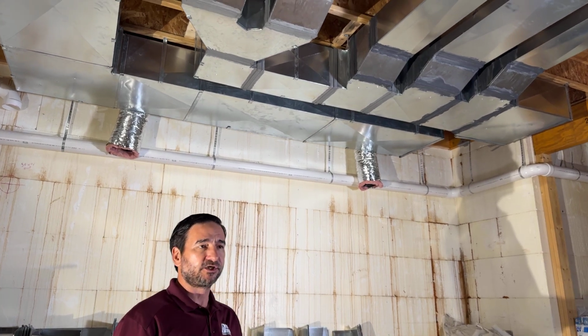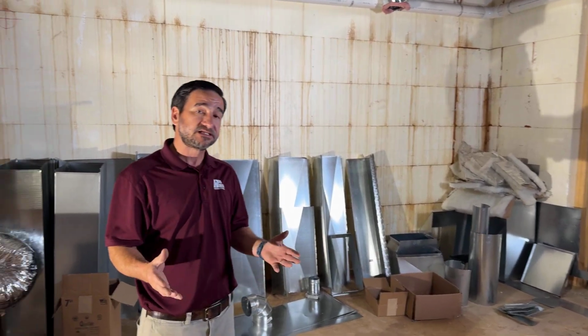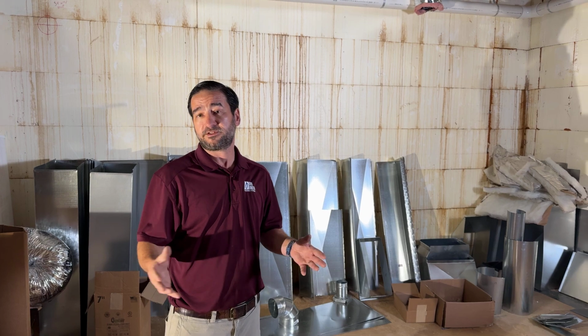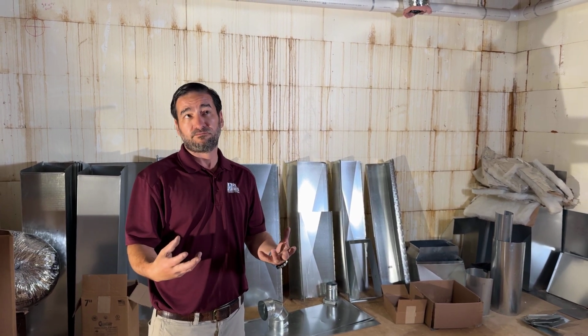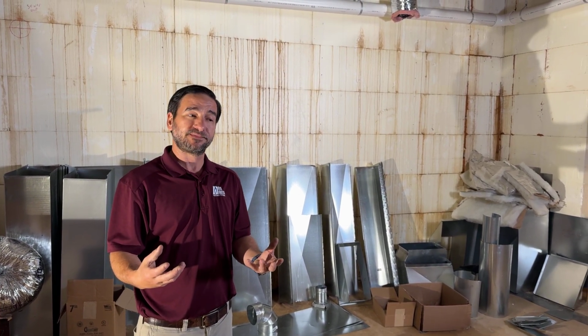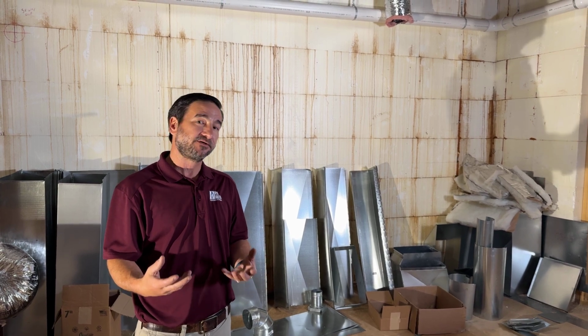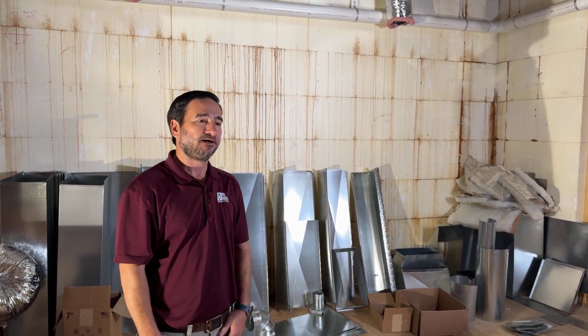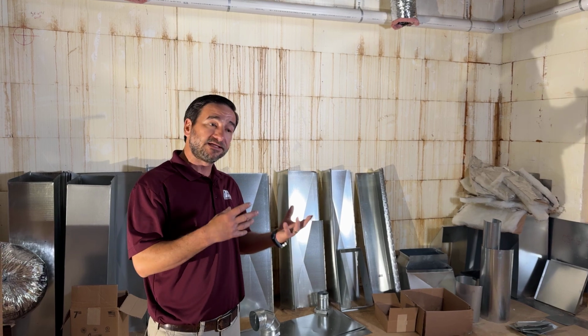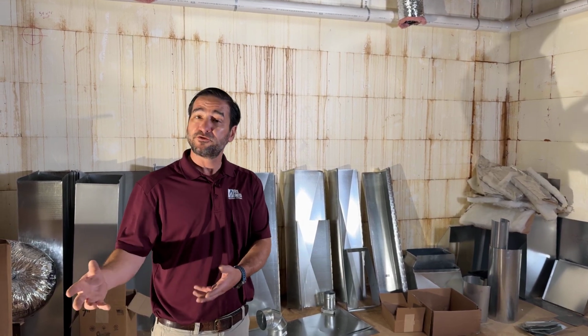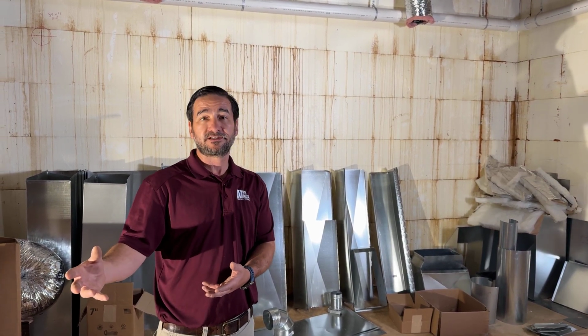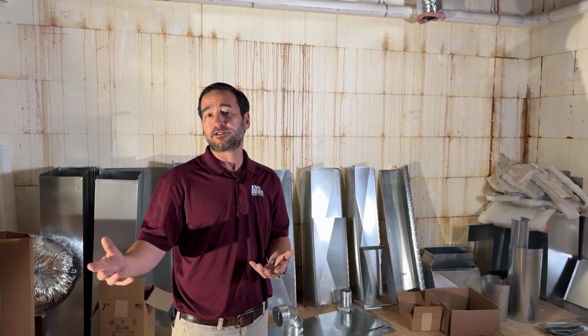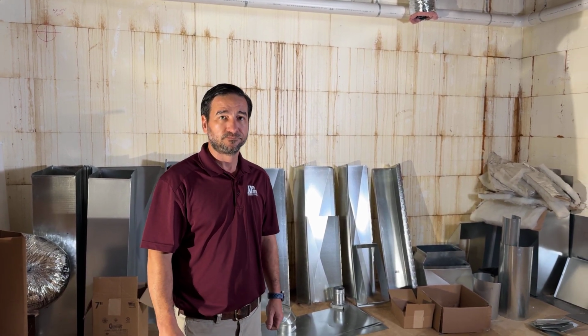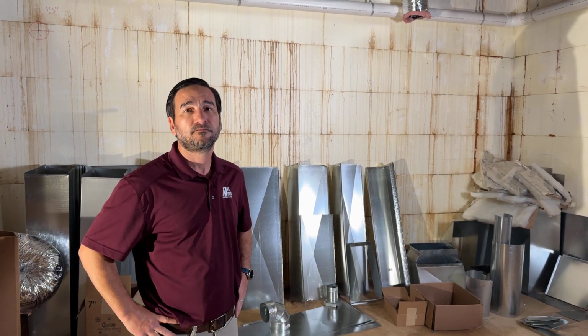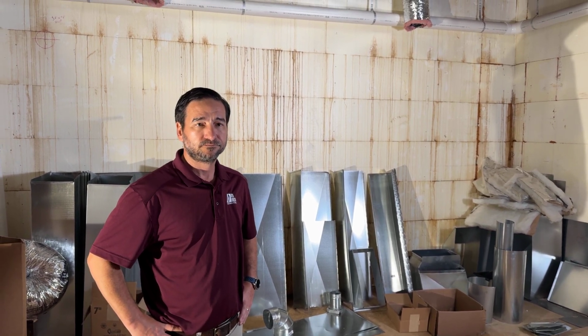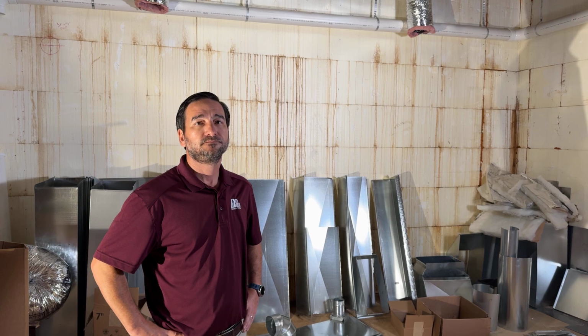So I usually encourage people, I tell them that we can zone any system, but if you have a 10-year-old unit and we now add these controls to it, we're ultimately asking more of it. So we're probably going to reduce its life expectancy. And if you are replacing equipment and you think you may do zoning in the future, I strongly encourage them to consider multi-stage equipment because it's going to complement the zone system much better. So that's actually a good topic. If you want to just briefly explain, like, what is a multi-stage piece of equipment, whether it's a furnace or a heat pump, what does multi-stage mean?